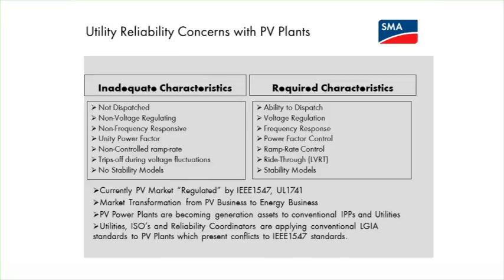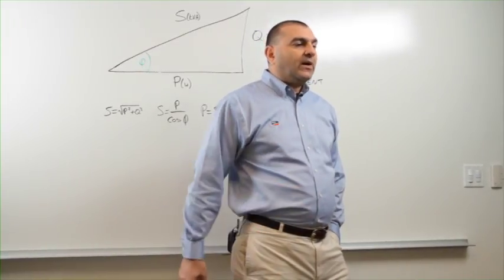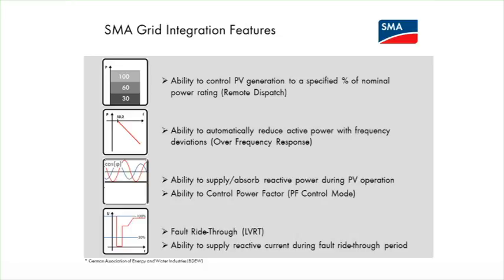For example, it's well known in the utility industry that inadequate characteristics of PV are that you cannot dispatch it, it doesn't regulate the voltage, it's non-frequency responsive, it operates at unity power factor, it has variability with the ramps, and also, most importantly, it trips during voltage fluctuation, and they cannot do good stability model analysis on these particular plants. The utility would like to see some required characteristics that are used in operating a conventional power plant, and that includes features such as the ability to dispatch, the voltage regulation, the frequency response, the power factor control, the ride-through, and also the stability models to be able to analyze those plants in a reliable fashion.